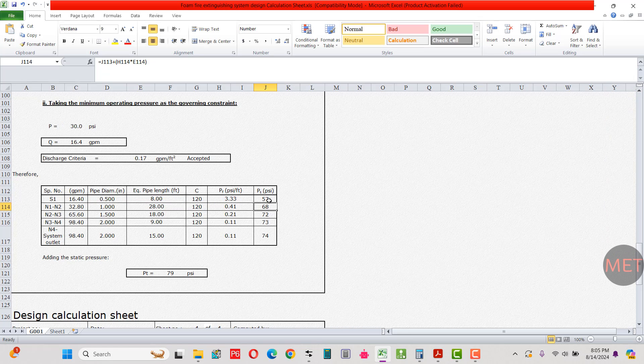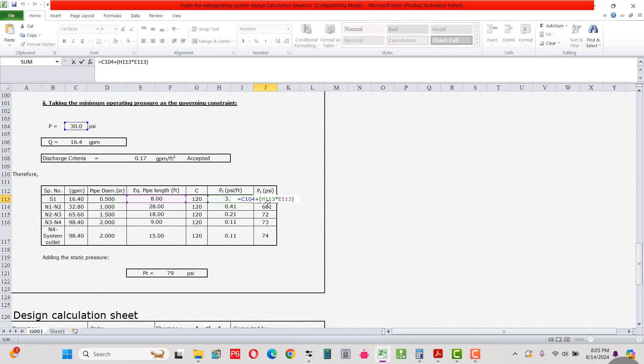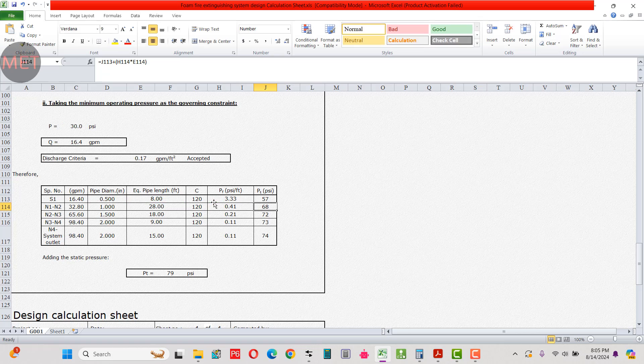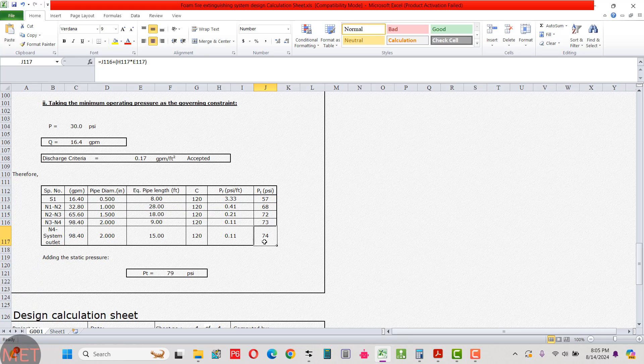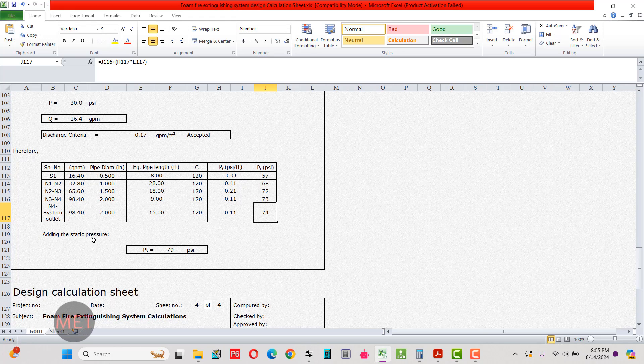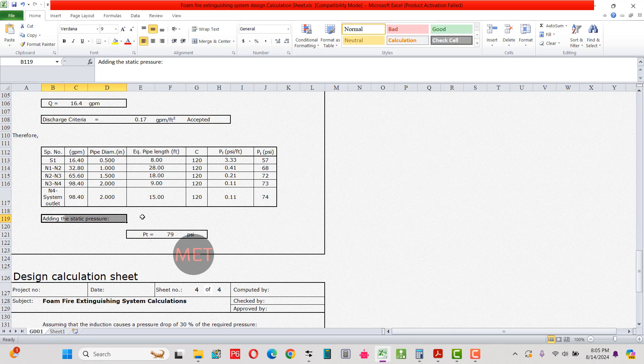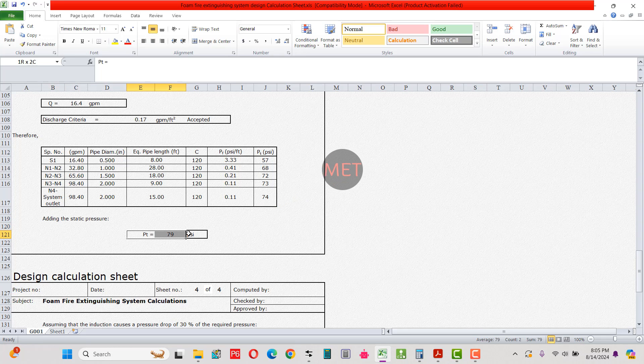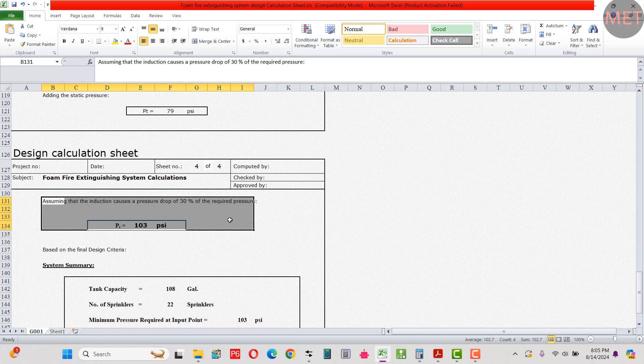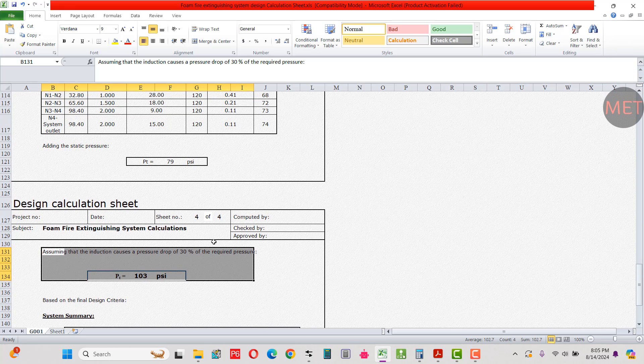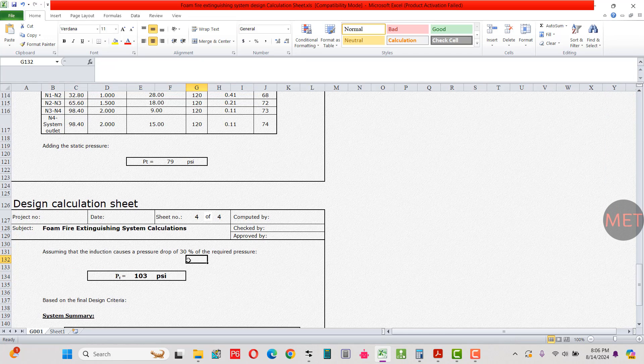To the 74 psi, we add 5 psi for static pressure losses, giving 79 psi. Then we apply a 30% safety factor to account for fittings, valves, and elbows: 79 × 1.30 = 103 psi total. So the three final design parameters are: foam tank capacity = 108 gallons, number of sprinklers = 22, and minimum pressure required at the input point = 103 psi.